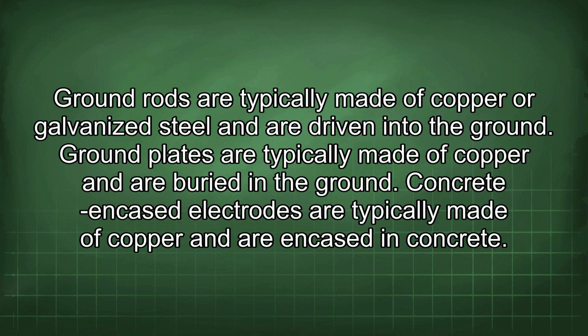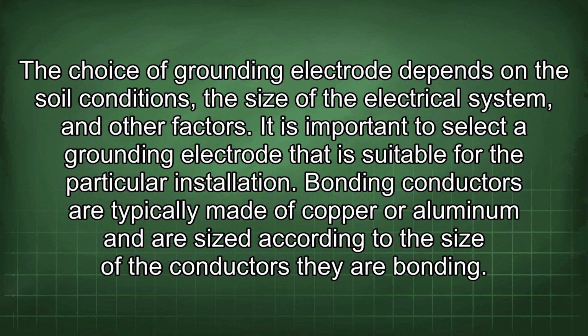Ground plates are typically made of copper and are buried in the ground. Concrete encased electrodes are typically made of copper and are encased in concrete. The choice of grounding electrode depends on the soil conditions, the size of the electrical system, and other factors. It is important to select a grounding electrode that is suitable for the particular installation.